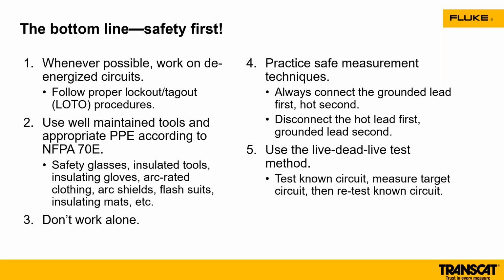Also, make sure that you're using the correct PPE. You're using the right PPE for the right environments. Make sure your safety glasses are up. You're using your insulated tools, insulated gloves, any of that arc flash rating that we talked about, the category rating of your gear. All of that helps. Don't work alone if you can help it. It's very difficult. I know when I was in the HVAC industry, a lot of times we were solo out there. We were doing a lot of service work, but at least check in with the front desk, check in with everybody to tell them where you're at and what you're going to be working on.